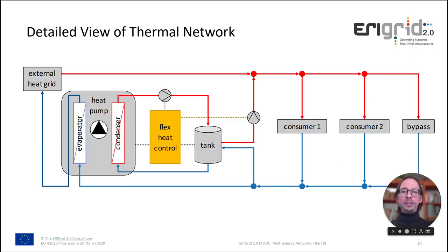A detailed view of the thermal network: you can again see the consumers. They are fed with hot water from the supply line, and the cold water returns to the external grid via the return line. The return line is also the cold water source for the tank and for the evaporator of the heat pump. The flex-heat controller controls two pumps — one moves hot water from the heat pump condenser to the storage tank, and the second moves hot water from the storage tank to the supply line of the thermal network.